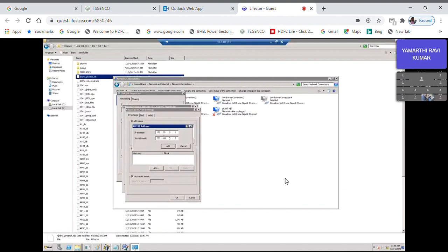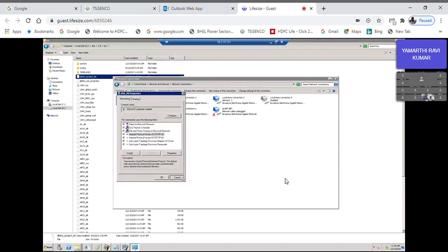If any ACN is not booting, we can go to BU directly and first check whether the DHCP server exists. If it exists, then the request from the ACN should reach BU automatically. Next step, even though the request is reaching and the ACN is not able to boot, then we have to check the system file of BU, whether the ACN hardware ID name is defined in it. Once all these things are there, the ACN should definitely boot.